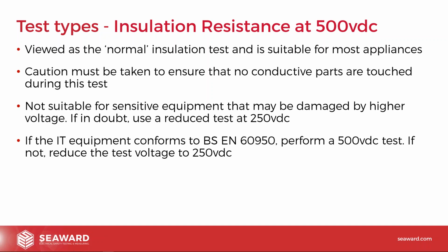So caution must be taken while doing the test to obviously make sure that we're not touching any parts, because the parts could become live during the test. We obviously also need to make sure that the equipment is switched on, so we're actually testing all the way through to the actual load within the equipment, and we're not just stopping at the main switch. We're not fully testing the equipment.